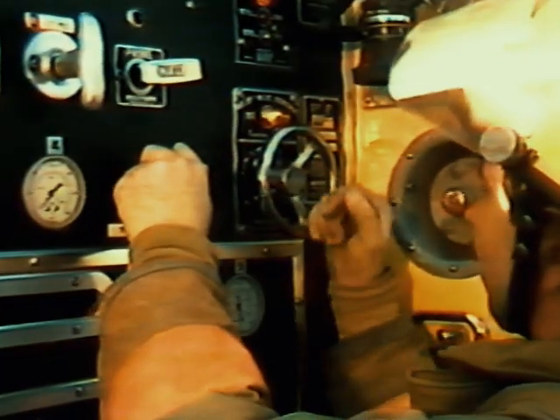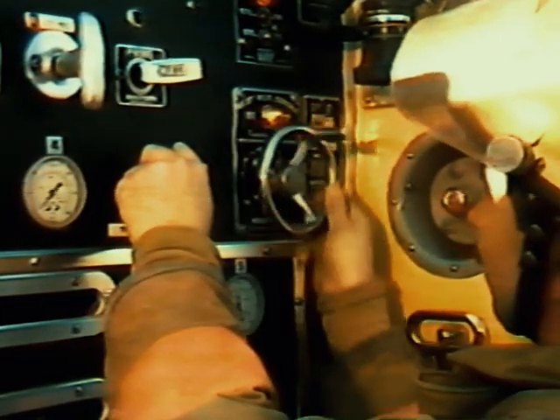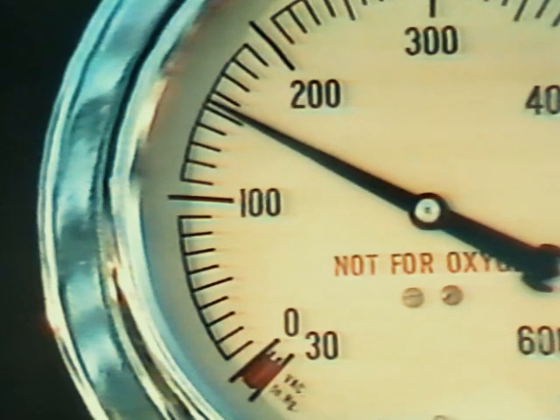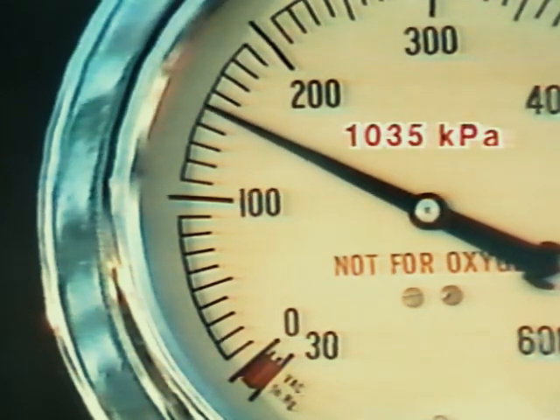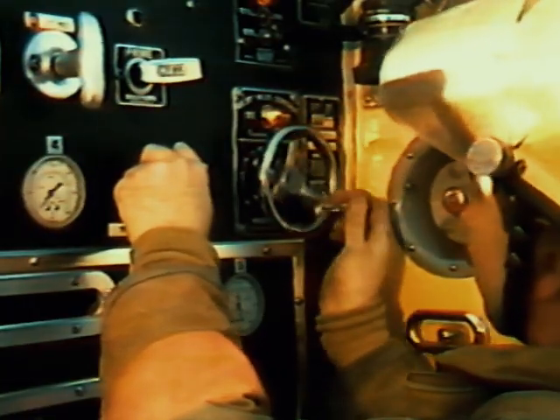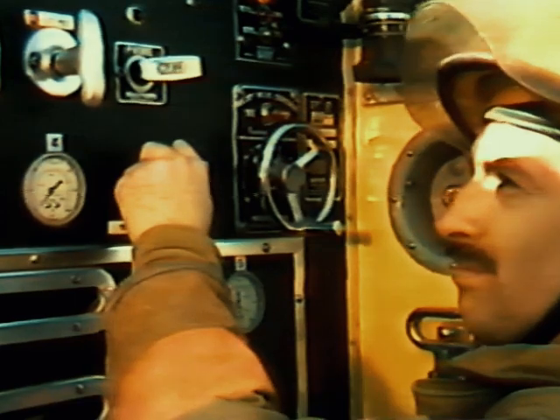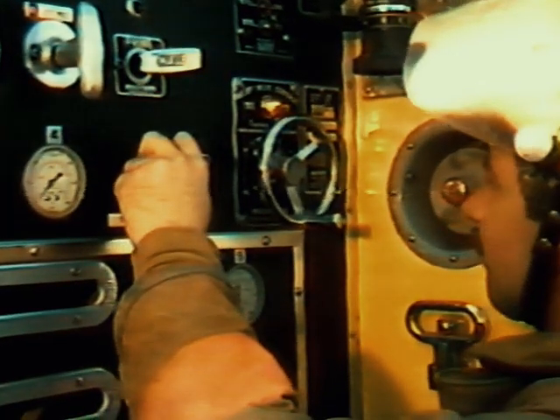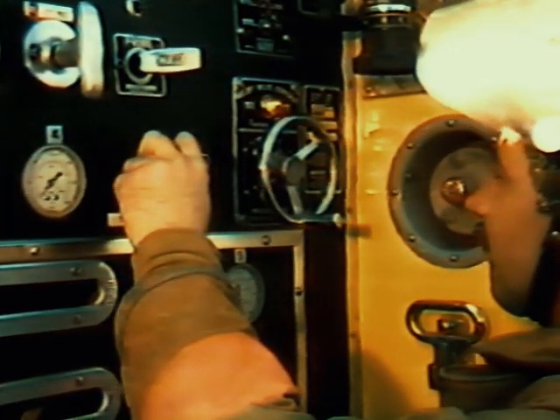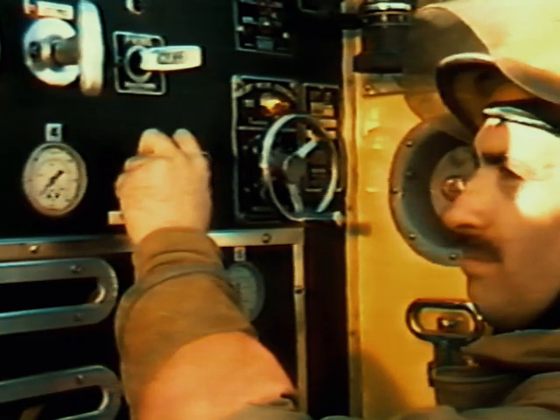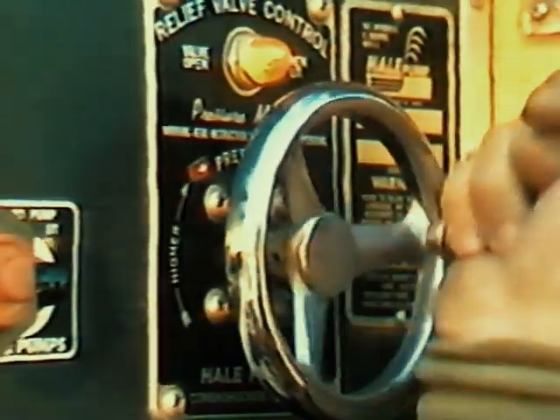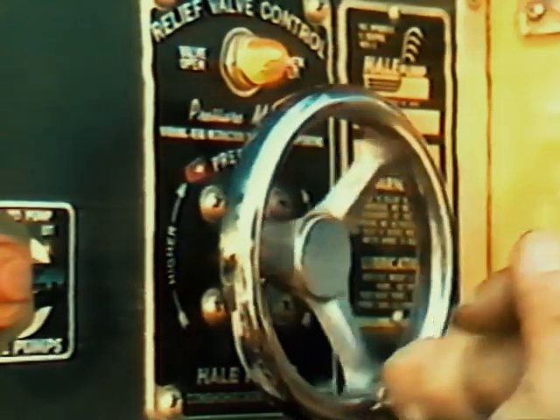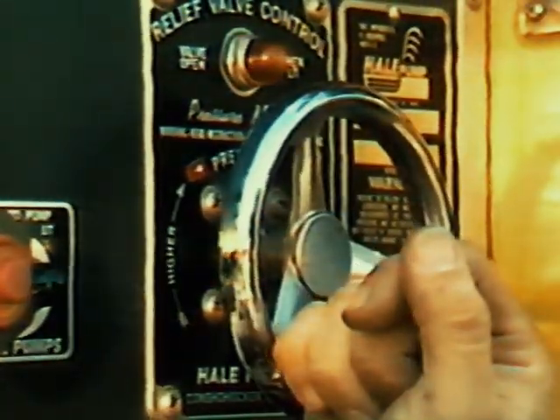Next, turn the control handle or wheel in a clockwise direction until the original pressure of 150 psi is reached and the light goes out. The relief valve is now set and will operate anytime the pressure exceeds this set value. Remember, you must reset the relief valve each time the operating pressure of the pump is changed.